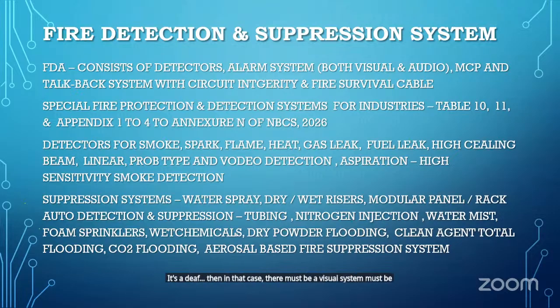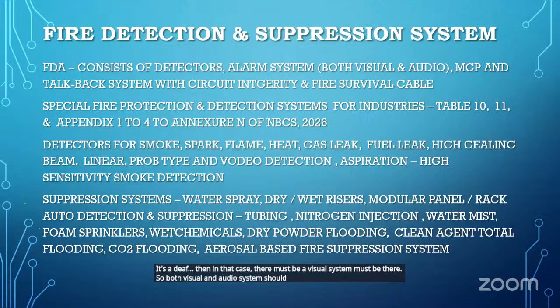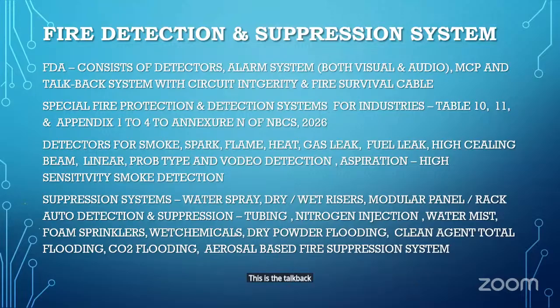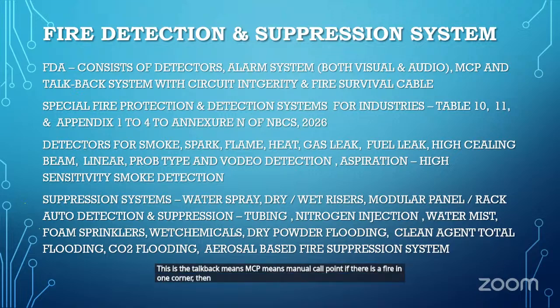So both visual and audio systems should be there, and that is the alarm system. And MCP, manual call point, and talkback system. MCP means manual call point. If there is a fire in one corner, then that person will break the glass or pull the pin, and that will connect to your emergency response center. Then it indicates there is a fire.